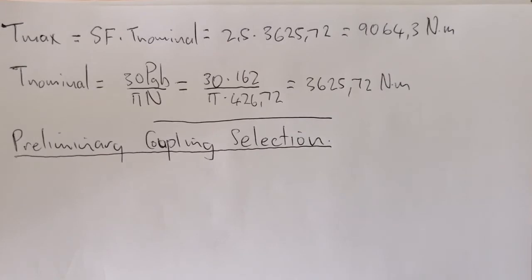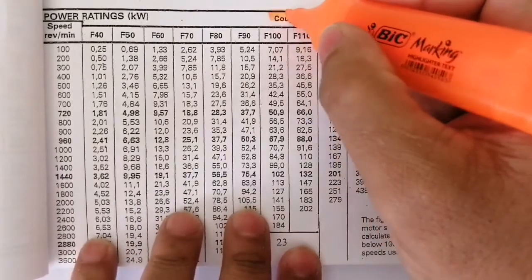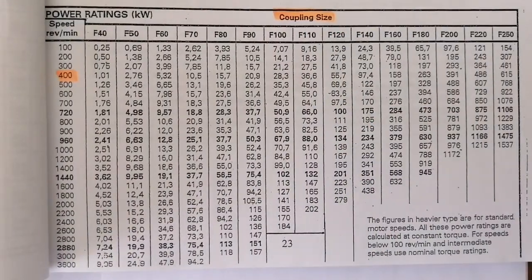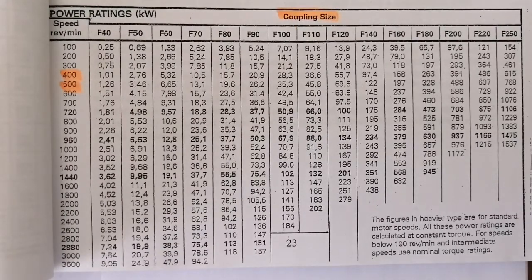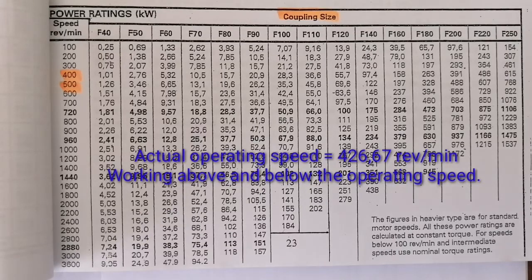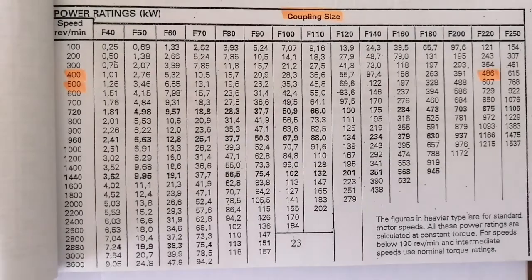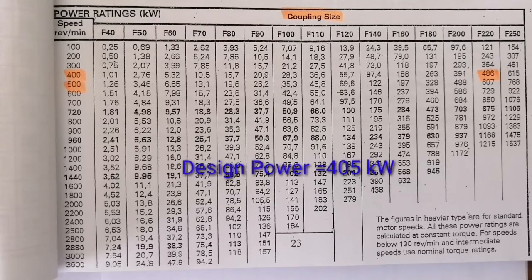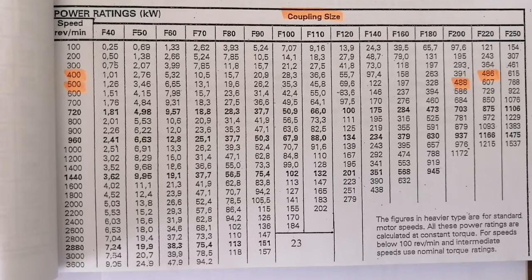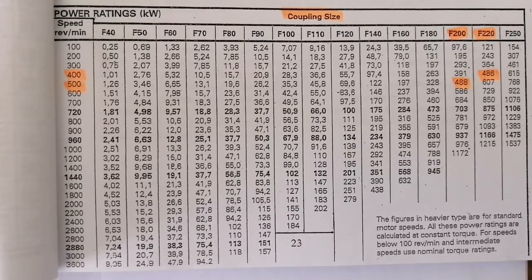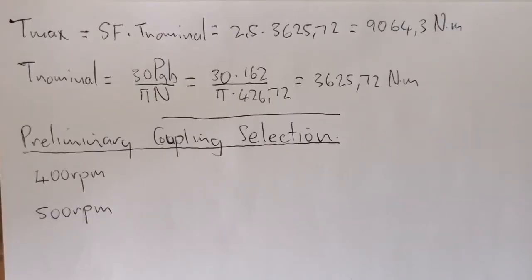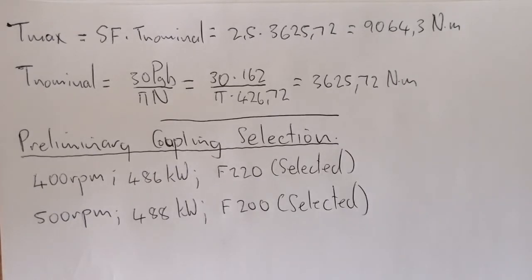Preliminary coupling selection - looking at the coupling size table between 400 RPM and 500 RPM, that's where our speed falls in. For 400 RPM, the power greater than the design power of 405 kilowatt is 486. For 500 RPM we have 488. This leads us to an F220 coupling for 400 and F200 for 500 RPM. Thus our preliminary coupling selection is F220 for 400 and F200 for 500 RPM.